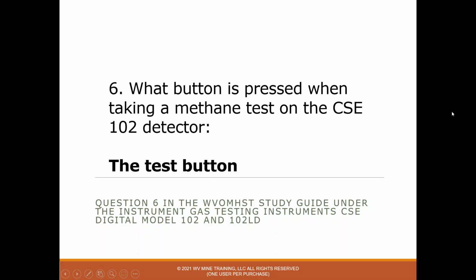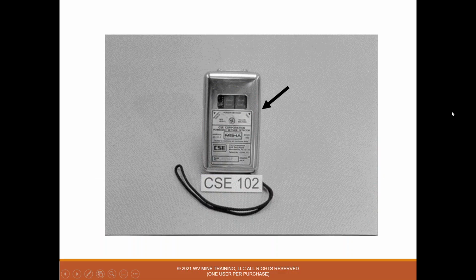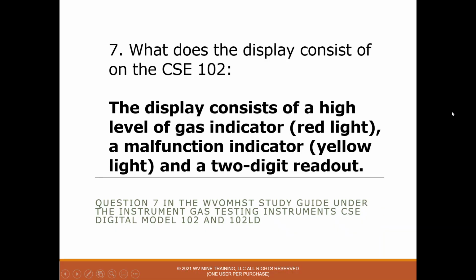Question 6, what button is pressed when taking a methane test on the CSE 102? And that is the test button only. This instrument doesn't work unless you push the buttons. And to take a test, you push the test button. Question 7, what does the display consist of on the CSE 102? And the answer is the display consists of a high level of gas indicator, that's a red light, a malfunction indicator, that's a yellow light, and a 2-digit readout.